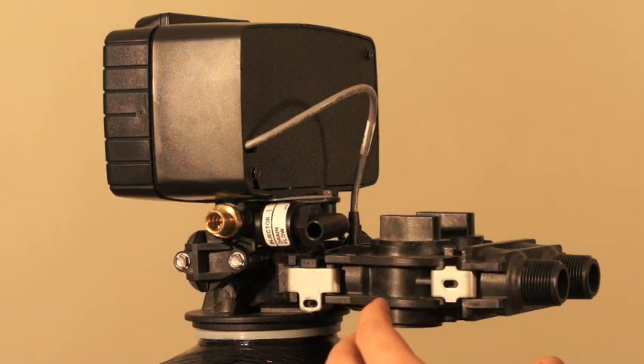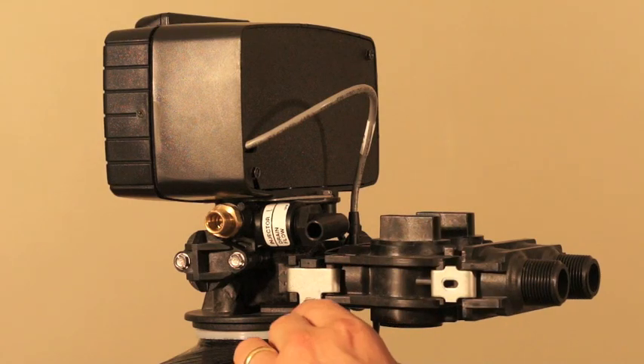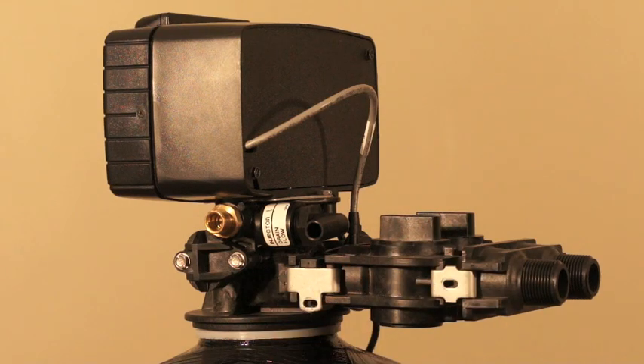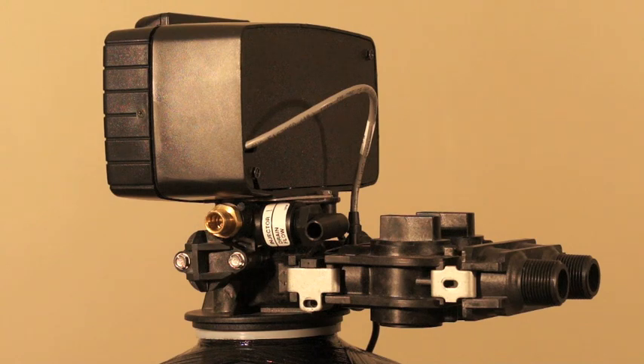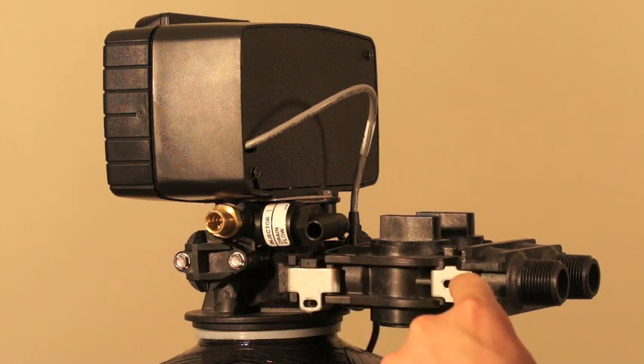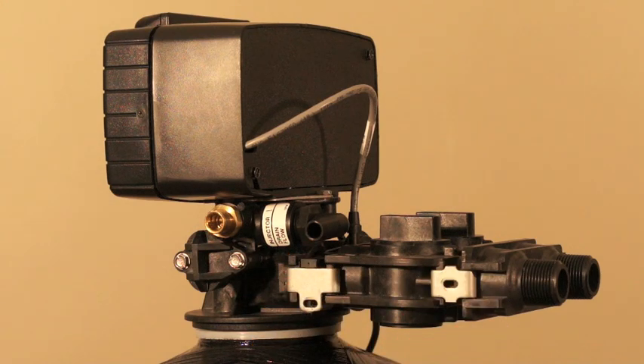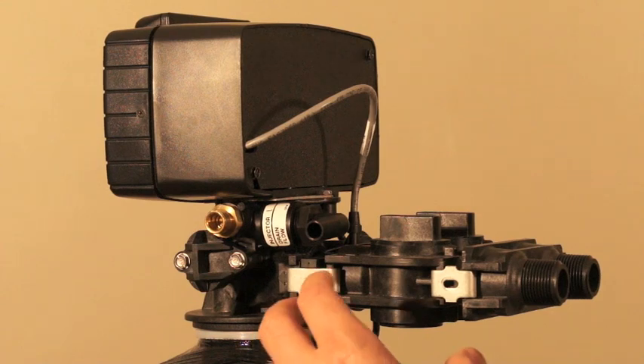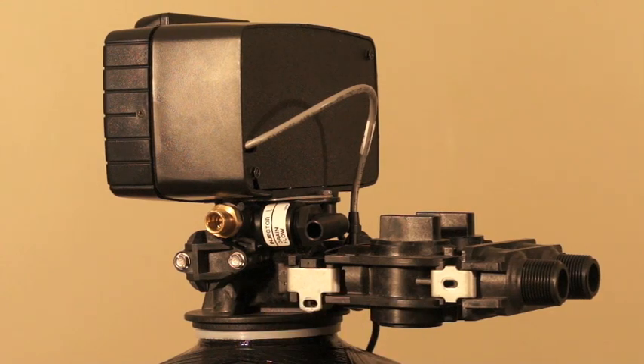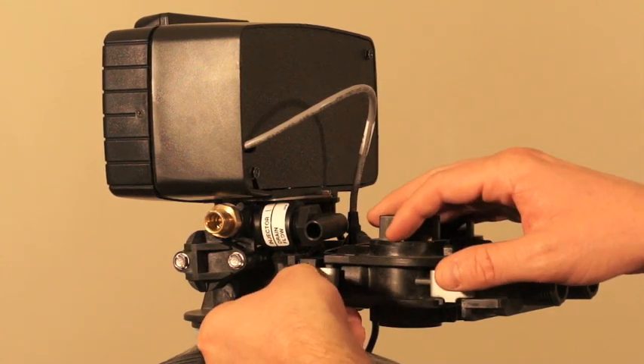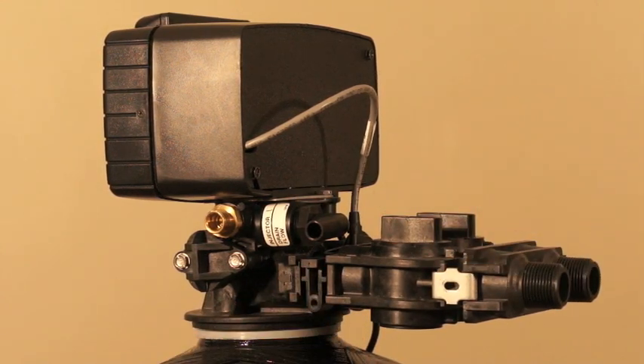It's O-ring sealed so you don't need to over tighten these screws when you put it back together. In fact, over tightening the screws can cause damage to either the turbine assembly or the bypass. So just snug them up just to hold that whole thing together. So we'll pull off these metal clips.